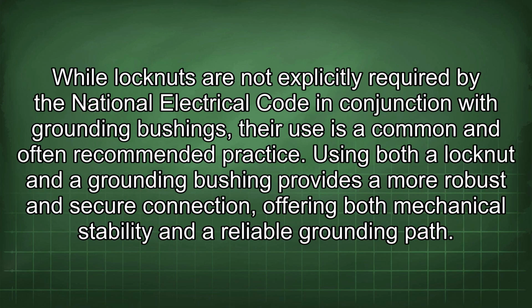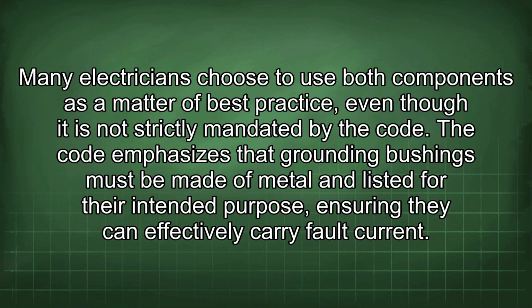While locknuts are not explicitly required by the National Electrical Code in conjunction with grounding bushings, their use is a common and often recommended practice. Using both a locknut and a grounding bushing provides a more robust and secure connection, offering both mechanical stability and a reliable grounding path. Many electricians choose to use both components as a matter of best practice, even though it is not strictly mandated by the code.